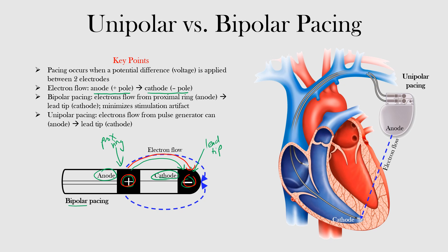With unipolar pacing, the anode is the pulse generator can — this area here. Electrons are flowing from the anode, the positive pole, to the cathode, which is the lead tip. So here's your cathode, the lead tip at the negative end, and the electrons are flowing from positive to negative — from anode to cathode in this direction.